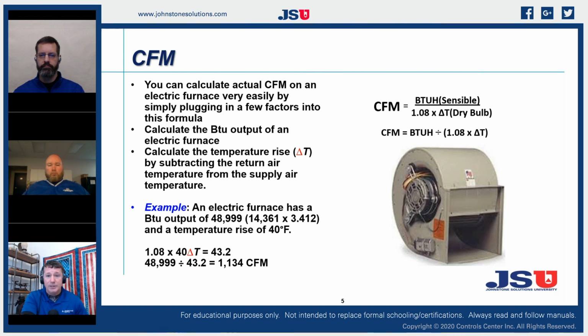Yeah, so the question was, does this include the compressor? Is this heat strips only? No, this is only our heat on our electric furnace. So this is while our electric furnace itself is running. So if this was a heat pump system with an electric furnace, we're going to have this in emergency heat so that we're not including the BTUs of our compressor, because that would actually throw all of our numbers off. So we're only doing this with our heat strip.